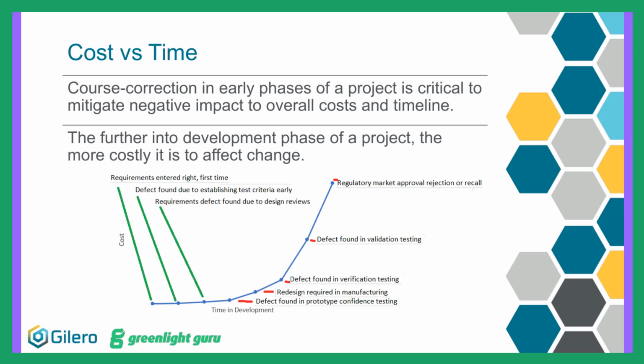Similarly, if wanting to do your risk activities late in the design process, the design may be too far along to add risk mitigations identified through this process, making it difficult to claim risk has been reduced as far as possible as required in the BS EN ISO 14971. In the worst case, your issues aren't found until your product reaches the field, and assuming that no one is seriously injured or worse, a recall is still a very costly activity to perform and impugns the effectiveness of your design control processes.